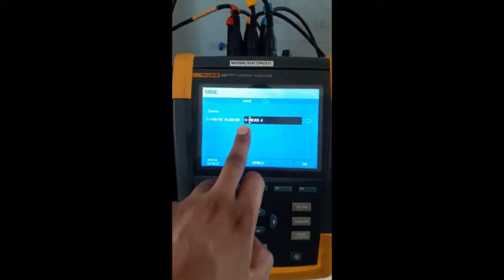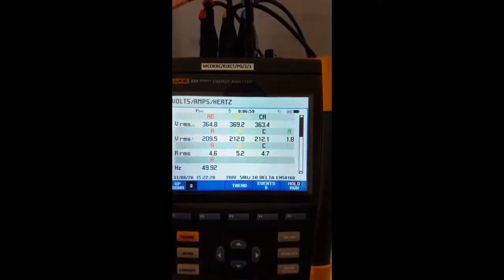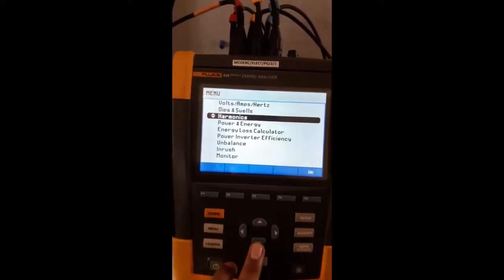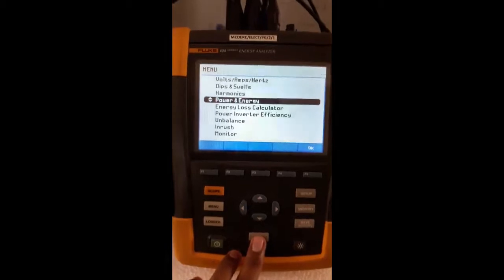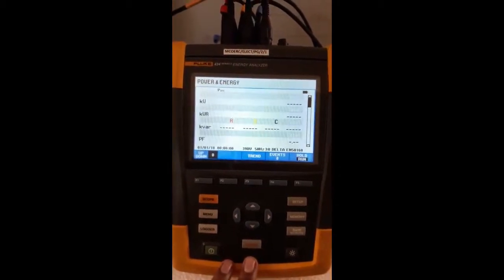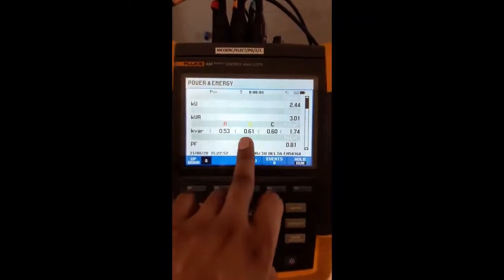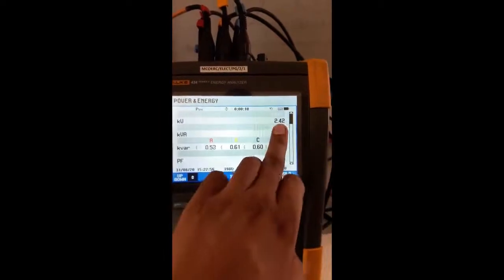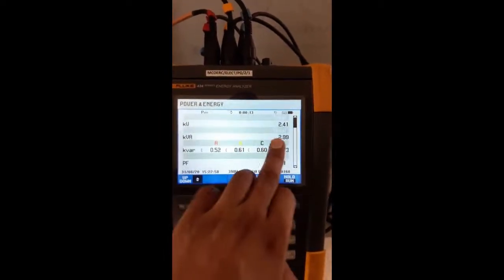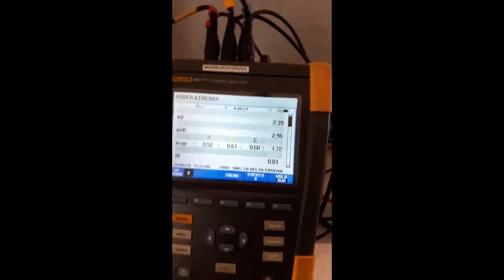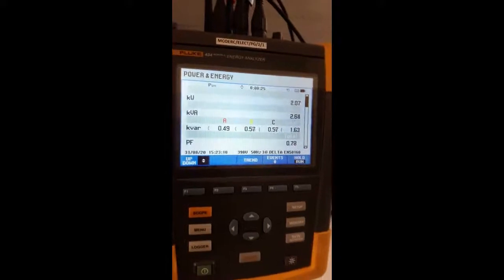Going back to menu and selecting power and energy mode, we can see the reactive power the motor is consuming. Total kilowatt power is 2.42 kW, kVA is near about 3, total kVAR is 1.74, and right now the motor is running at a power factor of 0.81. As the load is released, you can observe a decrease in power factor.